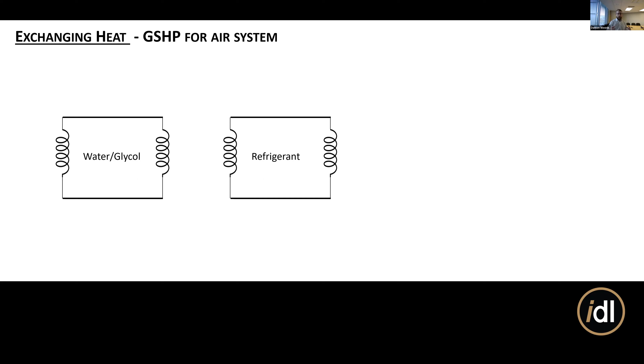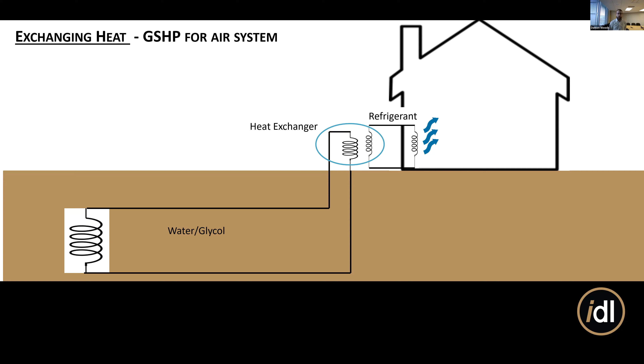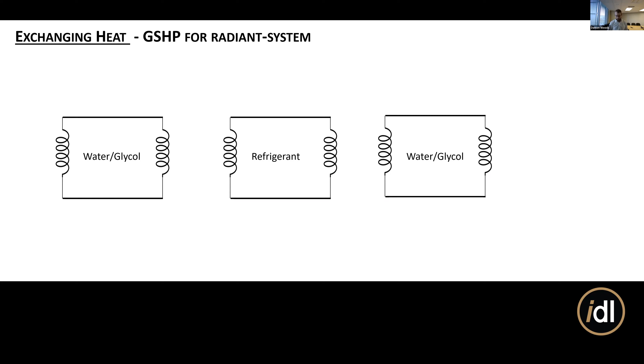So just expanding on this, you've got your coils buried out here, or these could be boreholes. Then you've got a heat exchanger where you're exchanging heat with one side of your refrigerant loop. This is where your compressor is going to live. And then on the inside, you've got your evaporator coil, and that's what your air is going to be blowing across for the system. If we wanted to connect this with the radiant system, we end up with 3 different loops, right? So we've got one water glycol loop outside. This is basically contained within our heat pump. And then we've got another heat exchanger here to exchange with the radiant system.